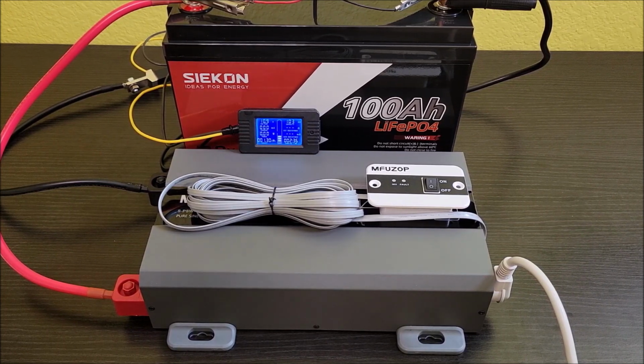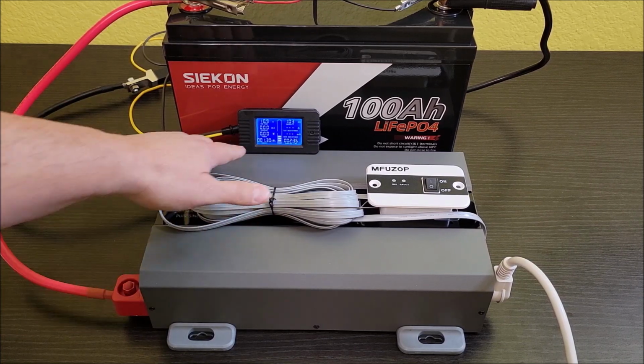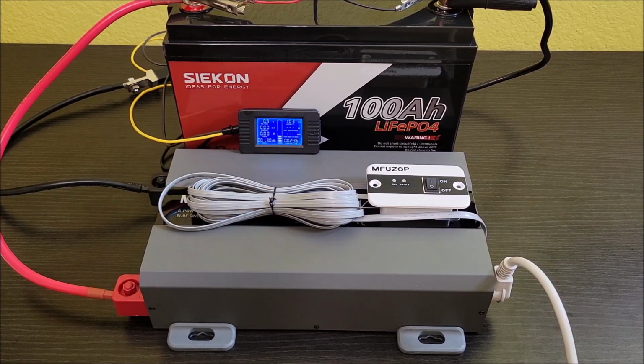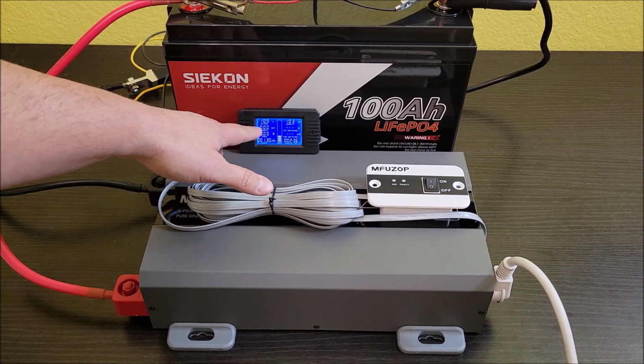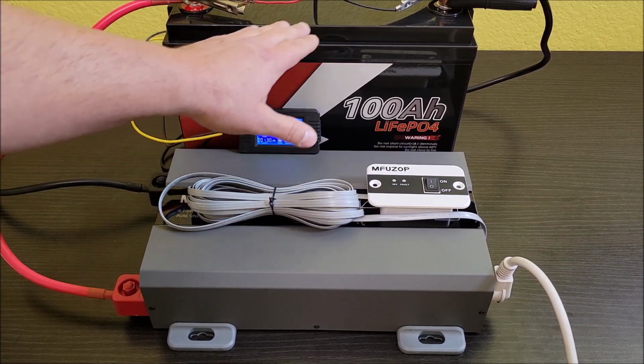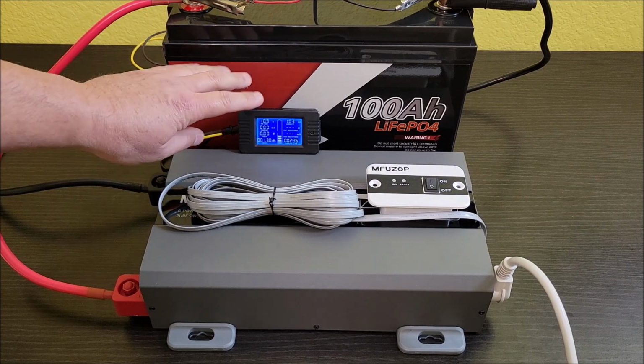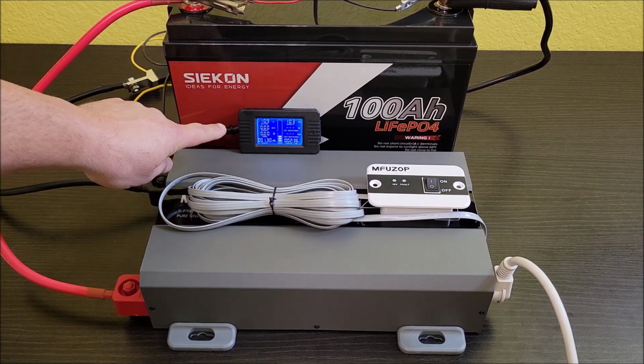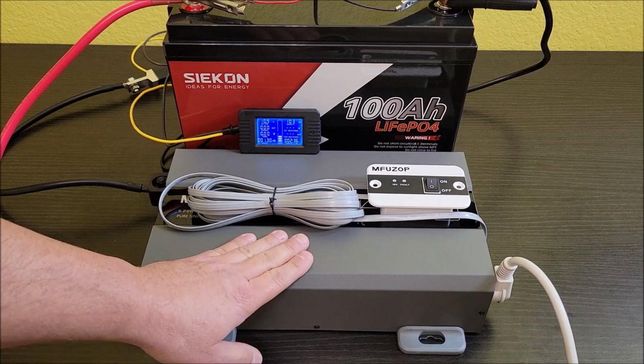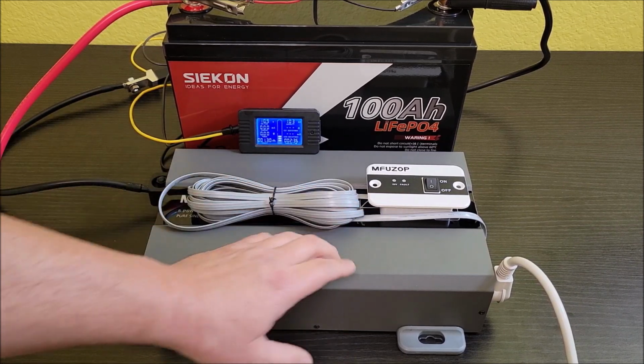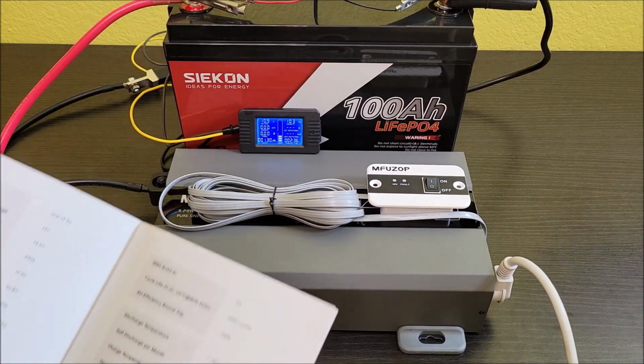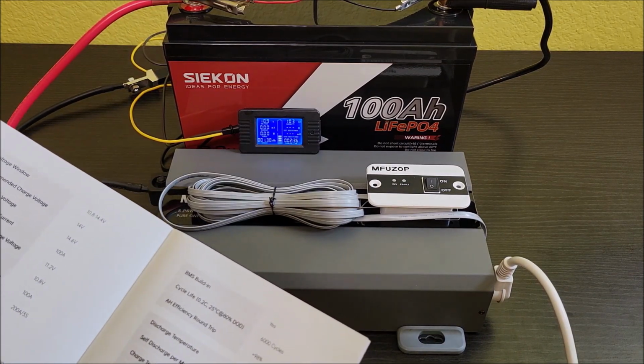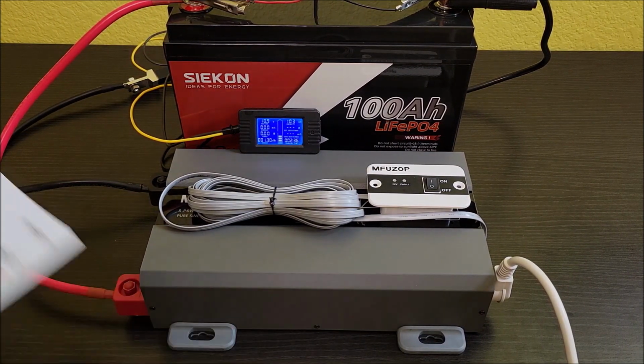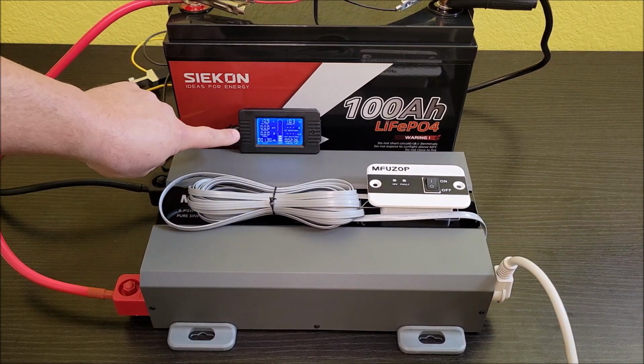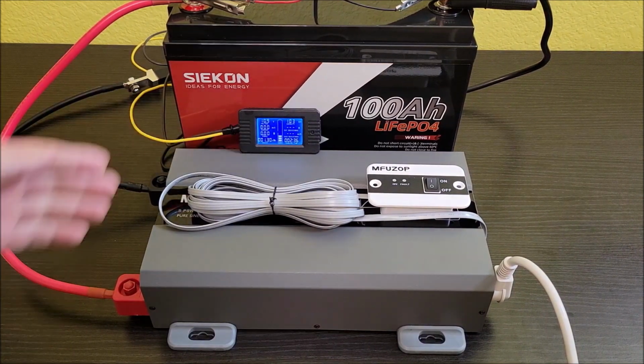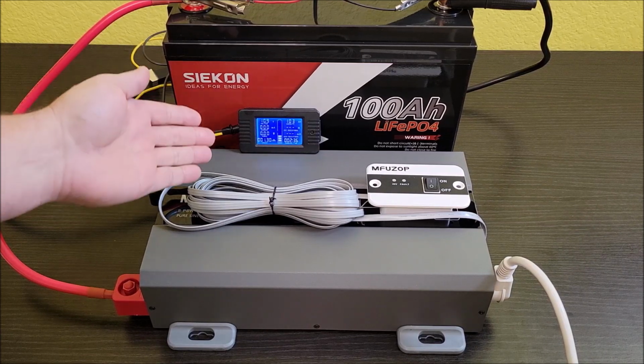And it's actually pretty impressive — 103 amp hours, 1.3 kilowatts. That's pretty good for a 100 amp hour battery. It's got 10.9 volts, so it didn't kick off the BMS, because if the BMS turned it off, this would have gone blank. But the inverter is basically what kicked it off, and that's why it faulted, because it detected low voltage. It does look like in the manual that its max discharging voltage is 10.8 volts, so this was just almost there for the BMS to kick it off.